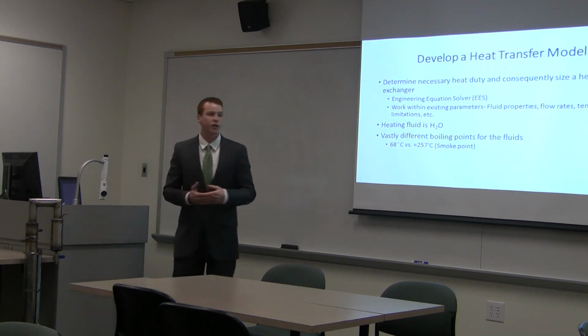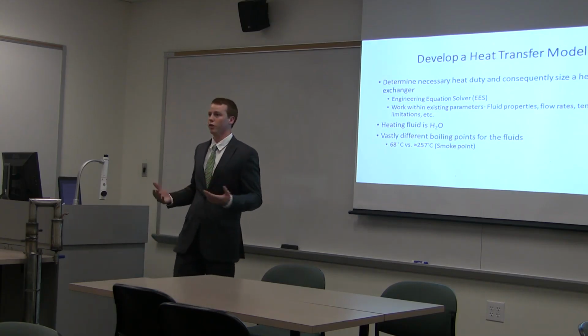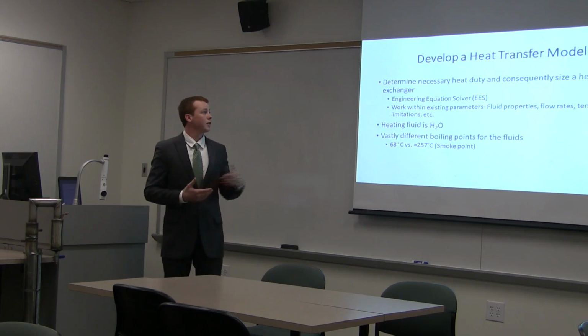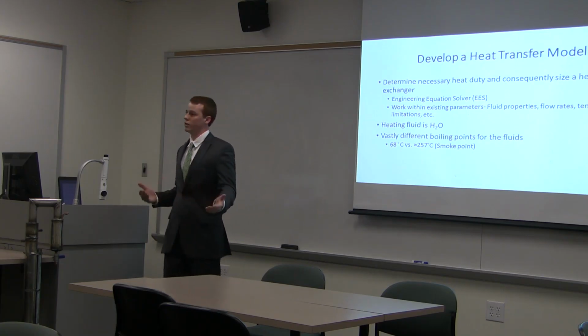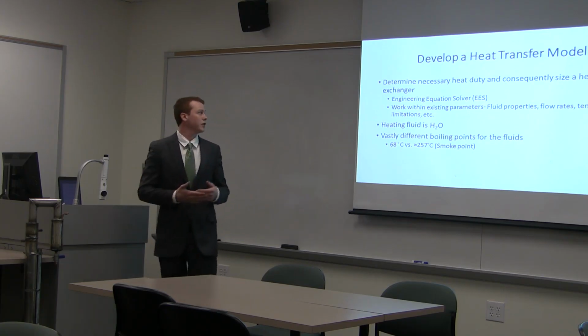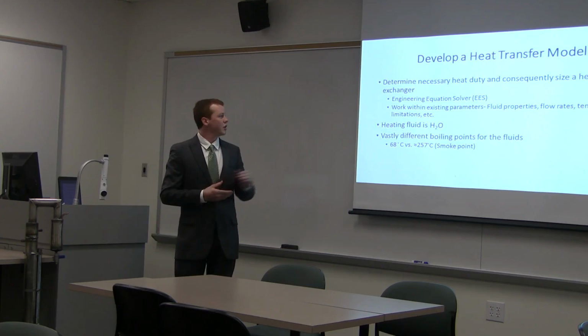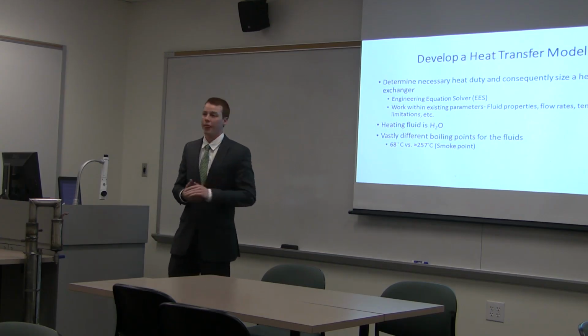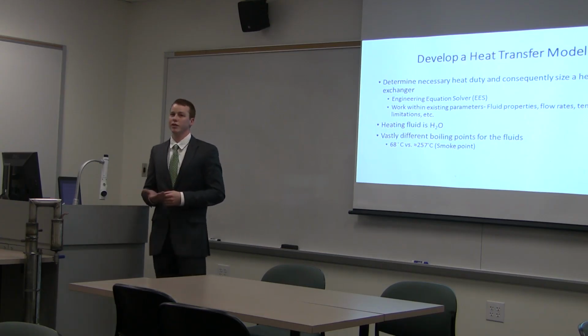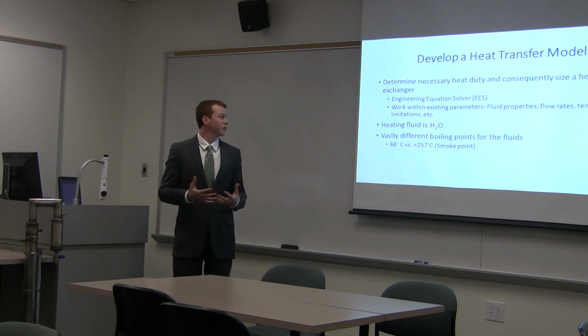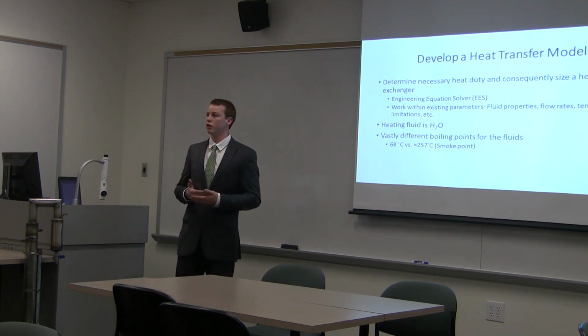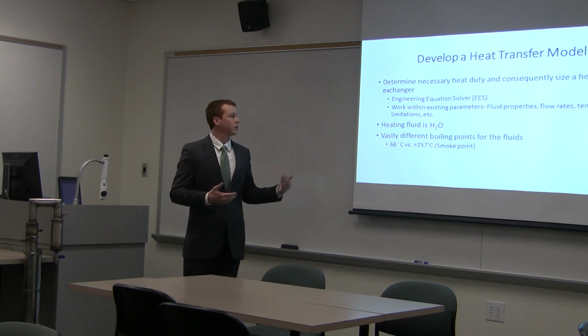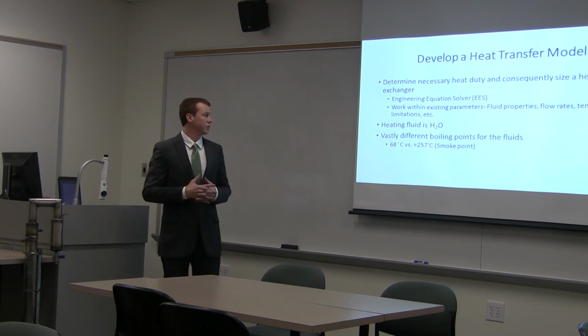There were certain things I just wasn't able to change—I can't change the specific heat or boiling point of these fluids, and I can't change the flow rate of the harvesting system. I need to work within these parameters, including temperature limitations, since our heating fluid is water and we didn't have the capability of distributing steam as a heating fluid. We need to keep that temperature under 100 degrees C while still providing the necessary heat transfer.